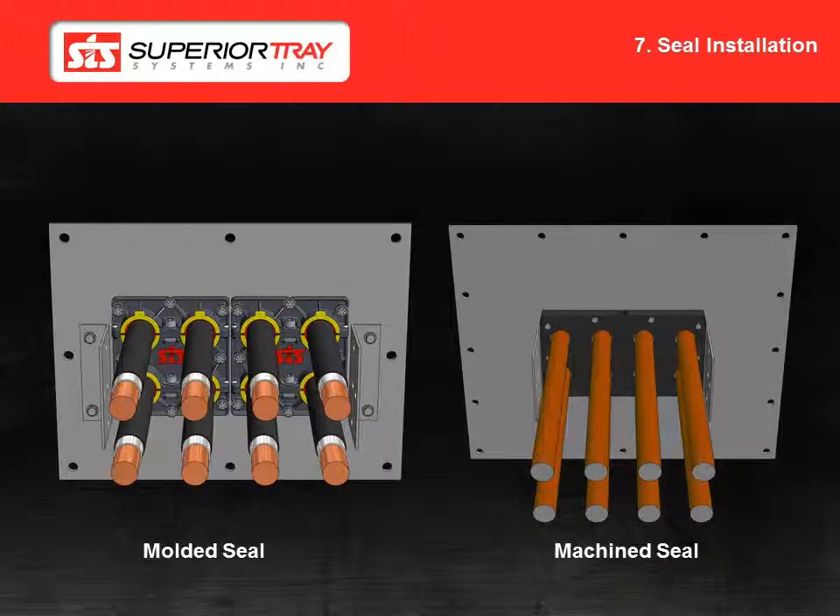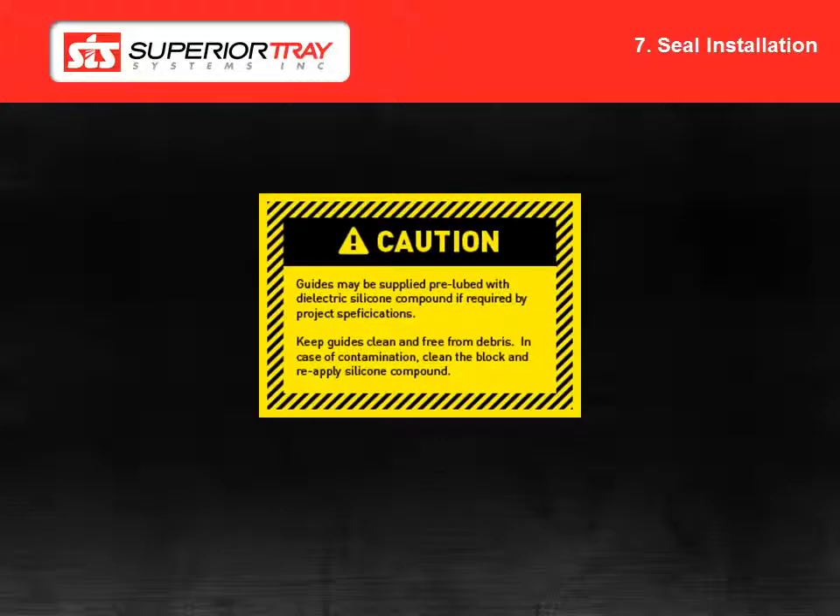In the following sections, we will show the installation of environmental seals. There are two types of seals: a molded seal and a machined seal. Please refer to your customer drawing package for information on which seal you have for your specific system. We will begin with the installation of the molded seal. It is important to know that the molded seals have been supplied pre-lubed with dielectric silicone grease. Ensure that the guides are kept clean and free of dirt and debris during installation. If the guides become contaminated, wipe the guide with a clean, lint-free cloth and reapply dielectric silicone grease.